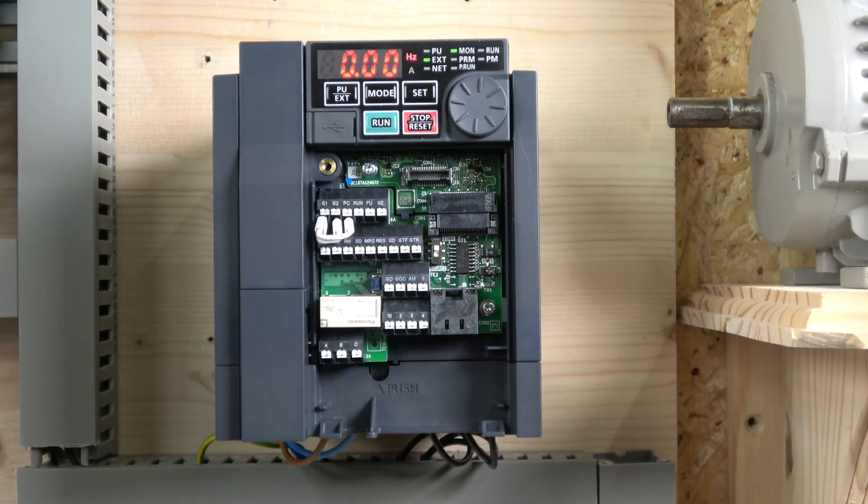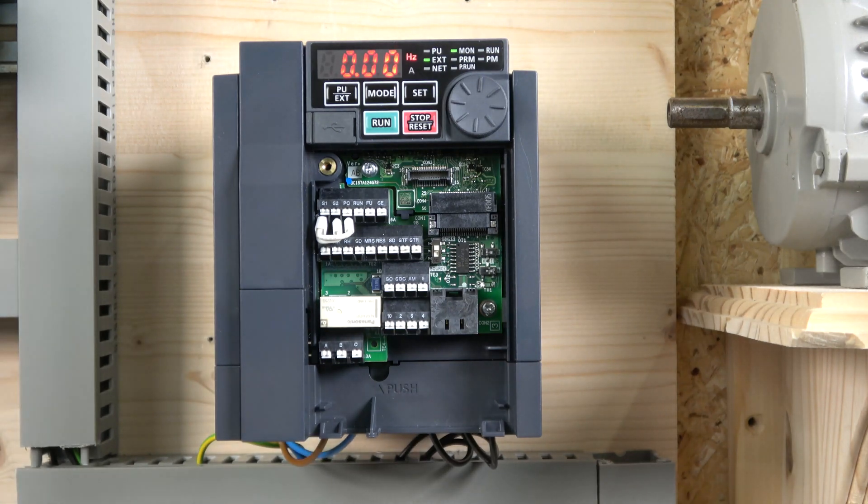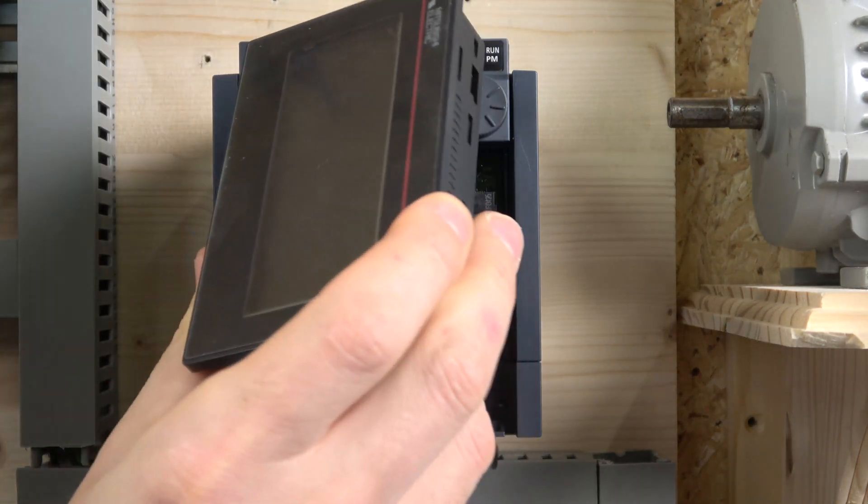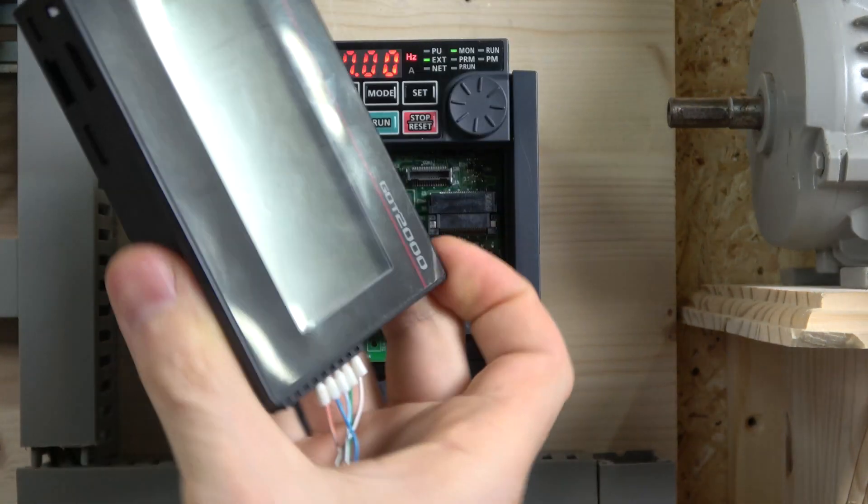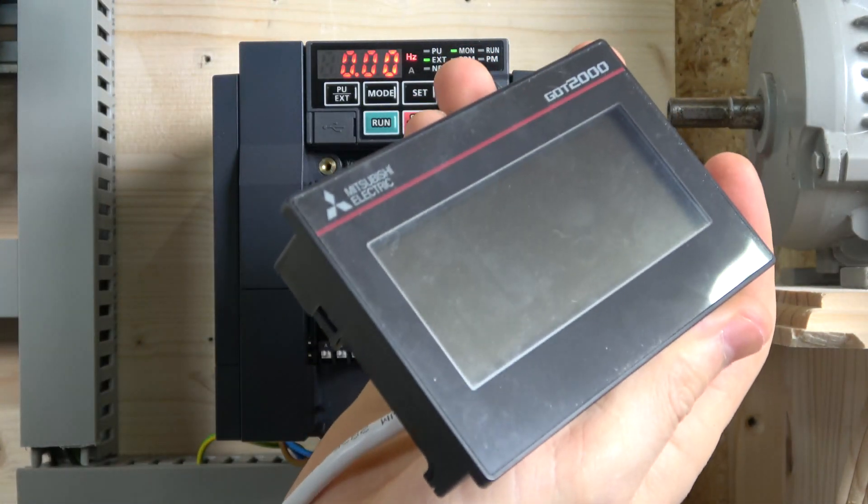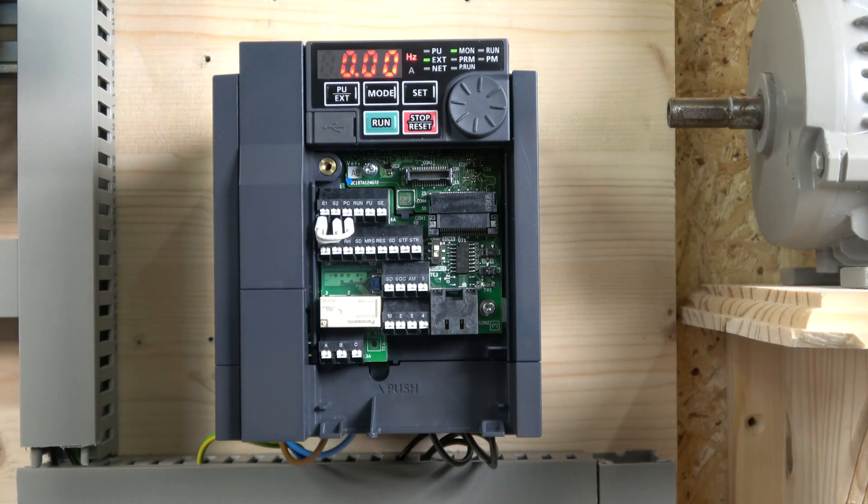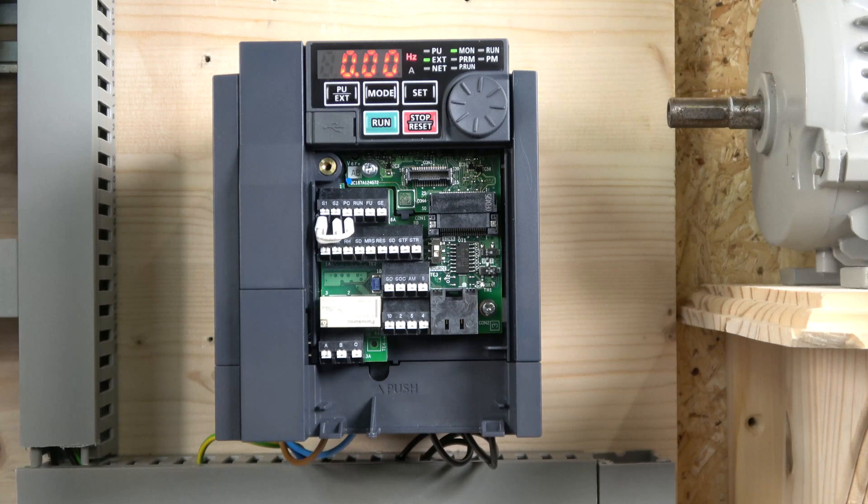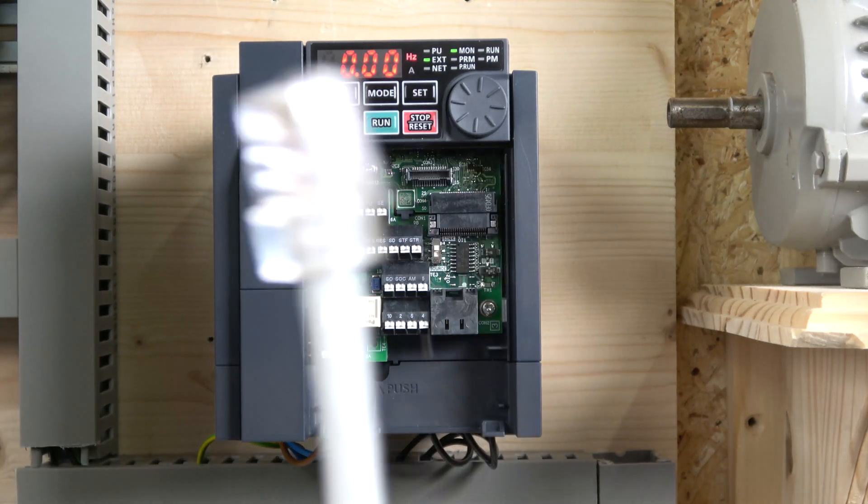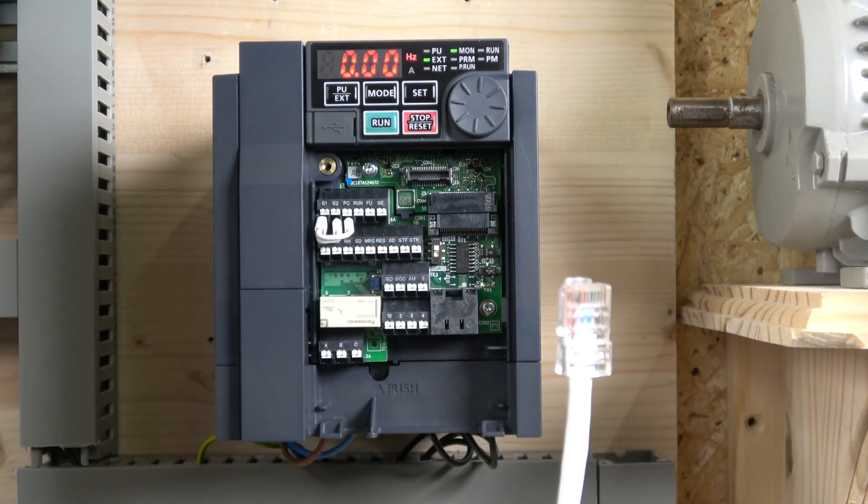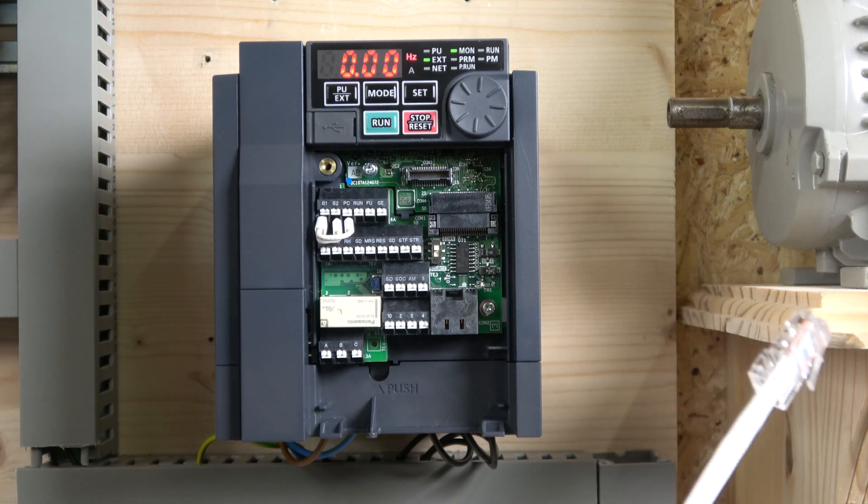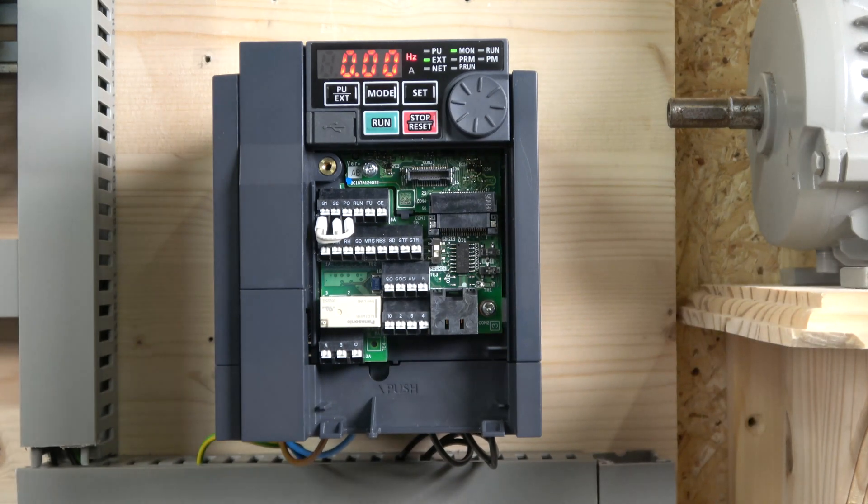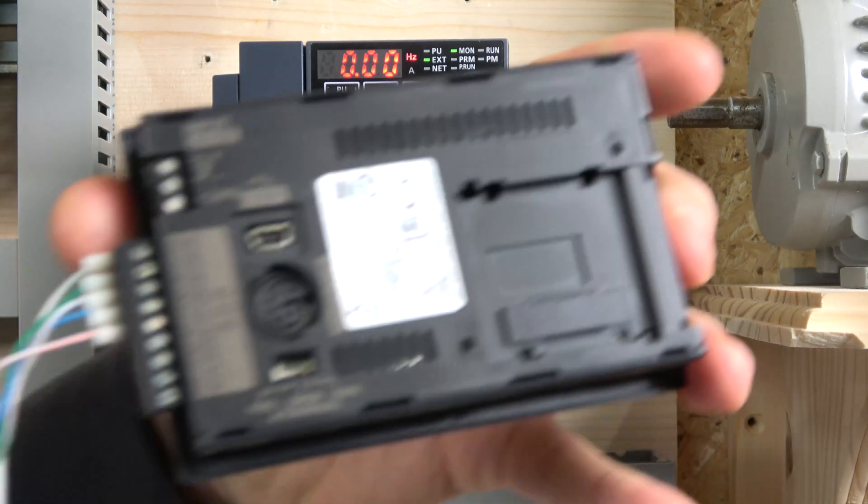The first thing we need to do is create a communications cable between this guy. I'm going to be using GOT2000, obviously yours might be different, so I'll show you later in the manual how to get your connection diagram. We're going to be using a standard RJ45 cable, which is a standard ethernet cable, chop one end off and do this kind of wiring.